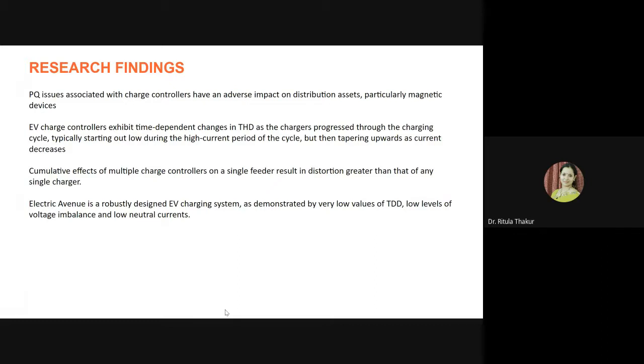So we have seen that during the initial 2 minutes of the charging, our current waveforms are perfectly sinusoidal. The THD components were very low. However, as the current decreases, so they tapered. As the charging came to approximately 80%, the third, fifth, seventh, and ninth harmonics increased a lot. And the cumulative effect of multiple charge controllers on a single feeder results in distortion greater than that of a single charger. So this also is one study that is but obvious.